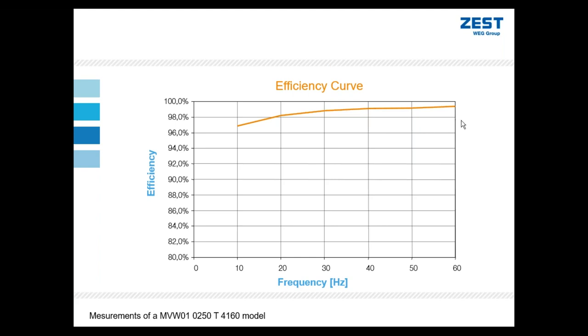The advantage, as I said, of this topology is that it is extremely efficient. You can see there more than 98.5, approaching 99% at nominal frequency. Because it's a voltage source inverter, the other advantage is that this efficiency curve is very flat. Even as we reduce speed, we still maintain a very high efficiency curve across the speed range.